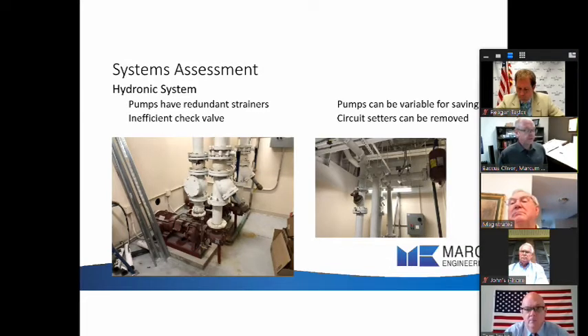These pumps have an inefficient check valve. You can see it in the photograph there. It's the wrong style to be a low pressure drop. And then in the right picture is a circuit setter. The characteristics of this type of circuit setter is a large pressure drop. Pressure drops just are energy wasters. They are what you have to have horsepower to overcome to move the water. So I believe there are some improvements that can be made to our pumping system.